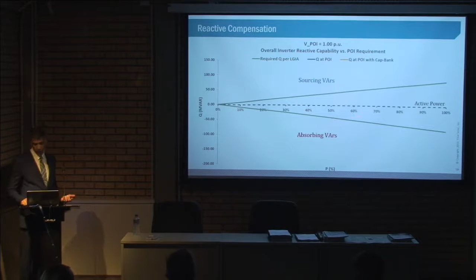When it comes to absorbing power, there is no major issue for the inverter. The inverter can handle that, but when you have to deliver power, at some point the inverter response is below what many utilities require. To fix that in a cost-effective way, you complement your inverters with a power plant controller and a capacitor bank, represented by this yellow line, adding more value to the client.